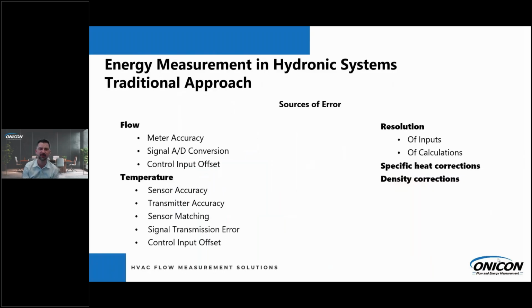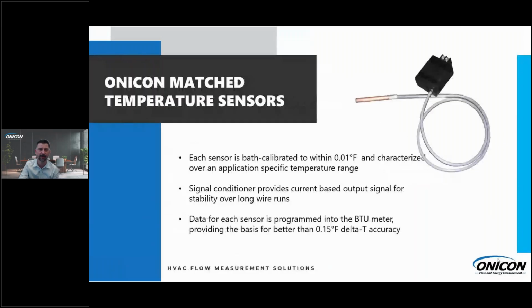And we found all these different sources of error from the flow meter, the temperature sensors, the calculations, and so forth. But we found out a lot of the inaccuracies was coming from the temperature sensors. So, you know, if you're using standard thermistors, RTDs, well, say it's a ½ degree off in the supply, and then a ½ degree off on the return. Well, when you're looking at that delta T, that's potentially 1 degree off, and 1 degree off in a 10-degree chilled water system, that's 10% error before you start considering the error from the flow meter and the calculations and so forth.